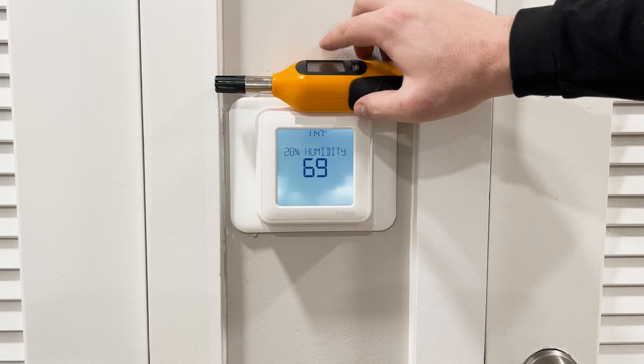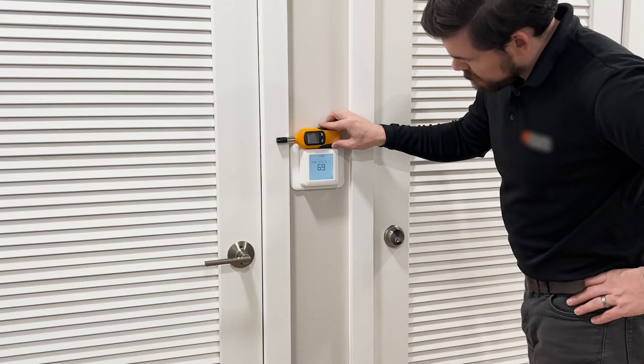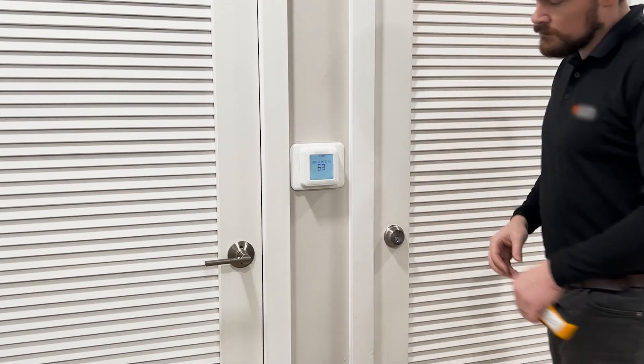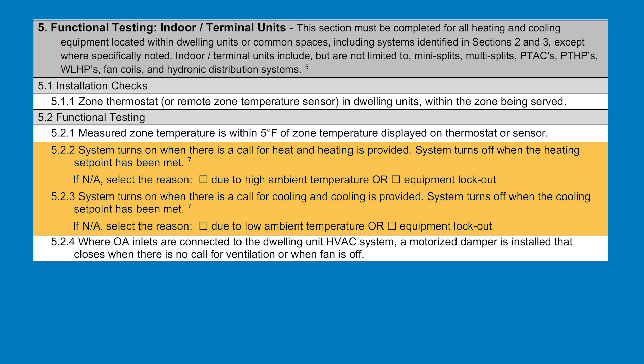Let the equipment acclimate to the room temperature. Once it hits steady state, confirm that it is within 5 degrees Fahrenheit of what the thermostat or temperature sensor is reading. For Sections 5.2.2 and 5.2.3, confirm that the system turns on when there is a call for heating or cooling, and then turns off when the set point has been met.